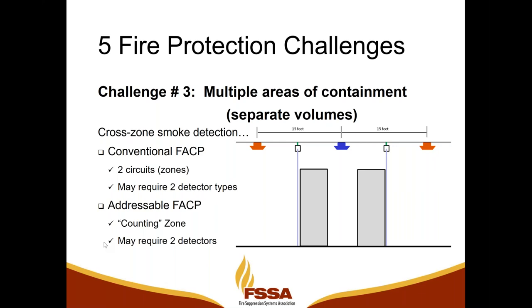For addressable fire alarm systems, we use a technique called counting zone. So it takes two detectors still. First detector comes in as first detection, second detector comes in as second detection. That, again, can slow down getting those two detectors to activate the system. So the smaller compartments that we build with aisle containment can impact detection and potentially slow the release of the gaseous suppression system.